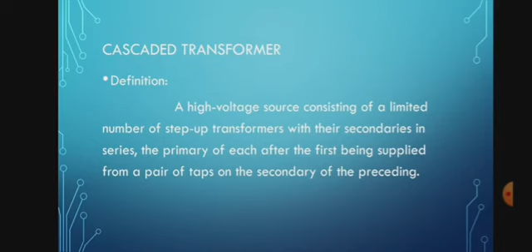Cascade transformers construction. The construction is identical for isolating transformers and the high voltage cascade units. All the cascade transformer units which are meant for the supply of excitation to the next stage have large leakage between the primary and the excitation windings.